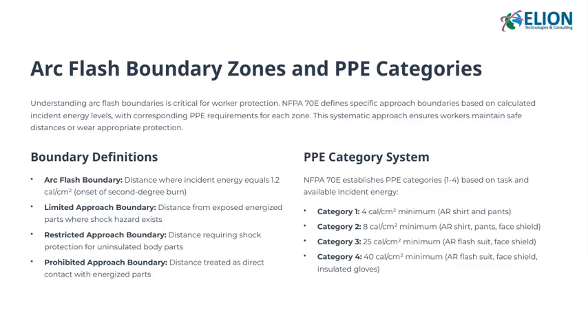And Category 4, the highest level, is for incident energies of 40 calories per square centimeter. It includes arc flash suits, face shields, and insulated gloves to provide maximum protection.